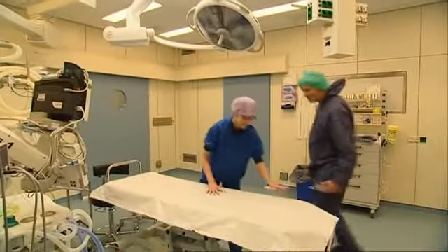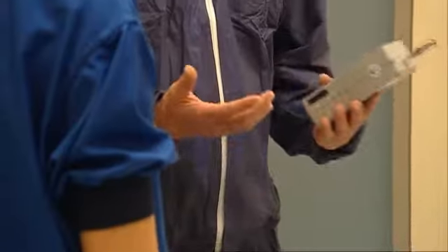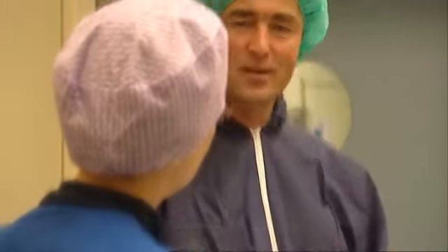The system continuously measures incoming and outgoing air currents and overpressure in all operating rooms, and the amount of door movements.